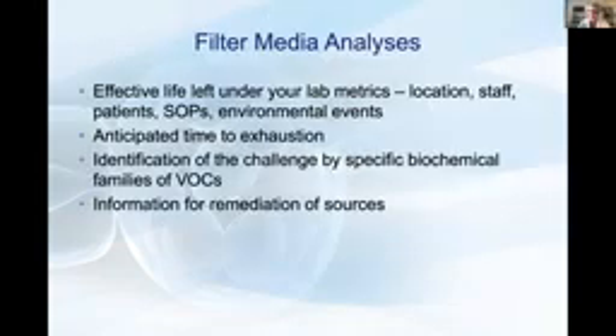Another tool that we've used is the analysis of the molecular media, or the used VOC filters. So you can determine, with the proper lab SOPs, basically the effective life left at the end of your use of your filter.